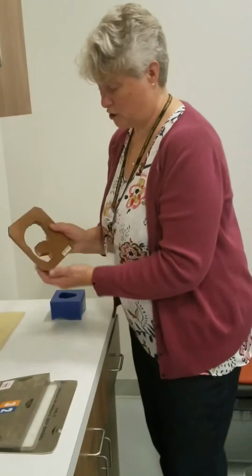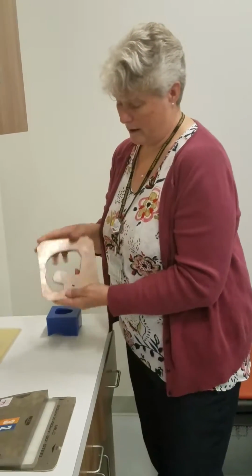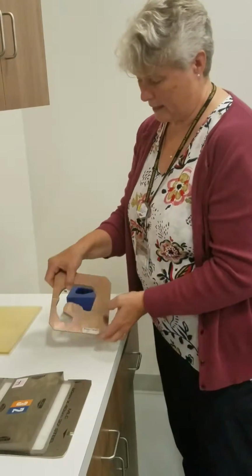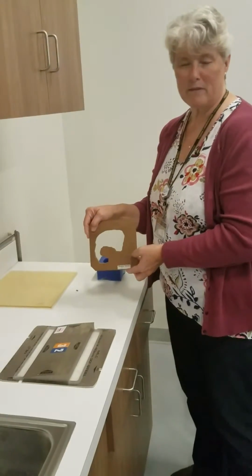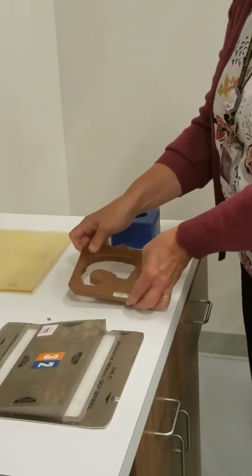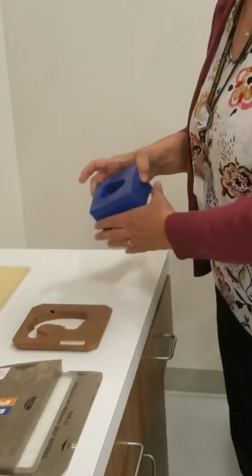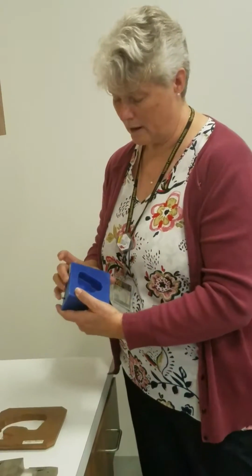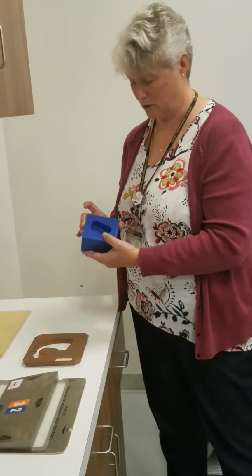This just shapes the beam. So if I can only create a square or a rectangle, things like this then further shape the beam to conform to the tumor that we're interested in. This is called a compensator, and this again would be milled to a specific patient. So this is for a single patient, nobody else could use it.